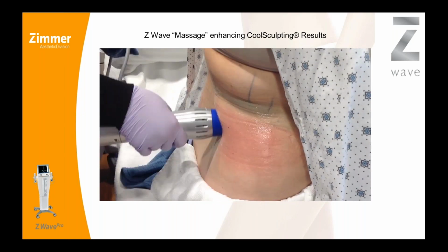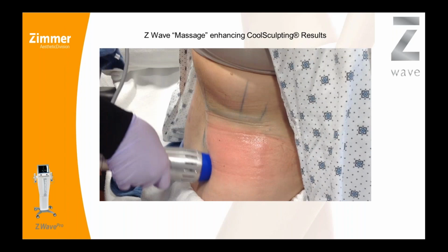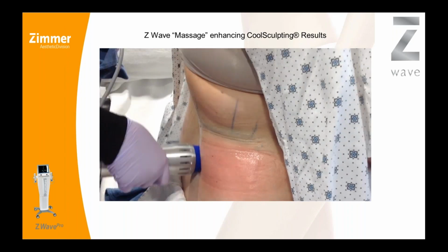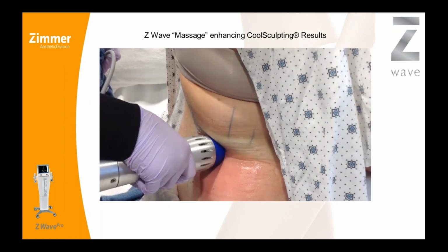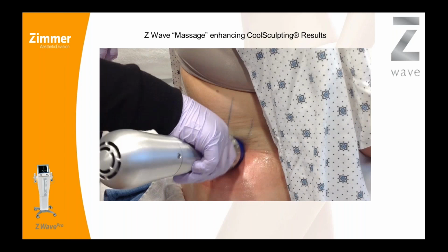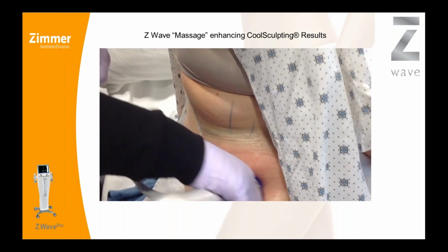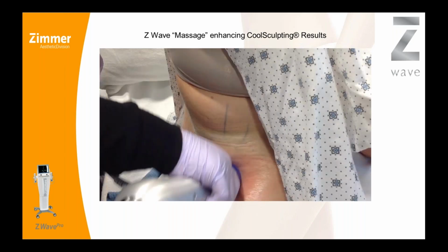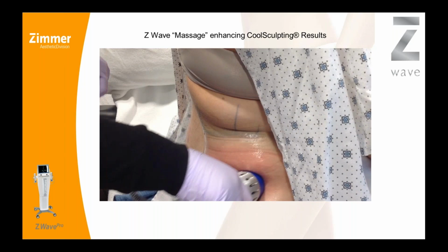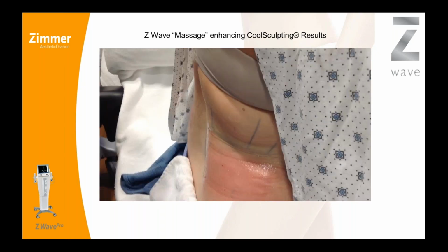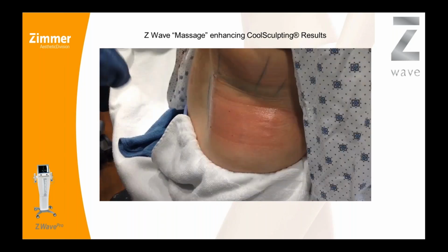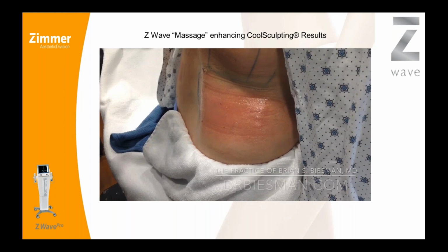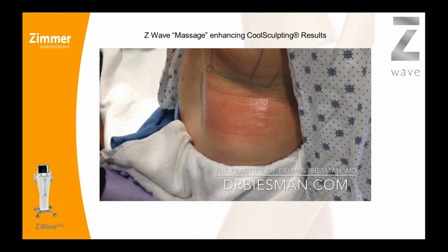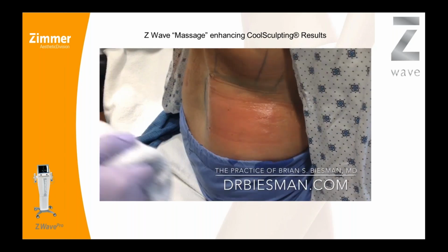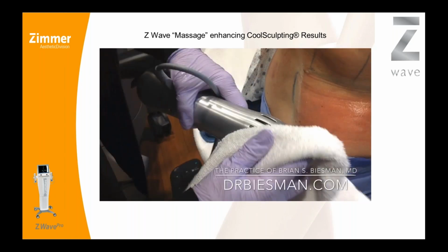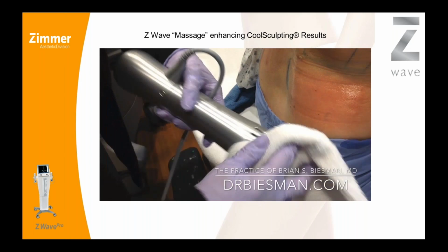And then at the end of your massage, simply wipe away any oil residue from the blue cap and place the handpiece in the holder cap side down. You want to avoid any oil entering the vents on the handpiece and wipe off your patient's skin and continue with subsequent treatments. After each patient, make sure you wipe the blue cap with alcohol. Don't use Sani wipe since that can destroy the plastic.